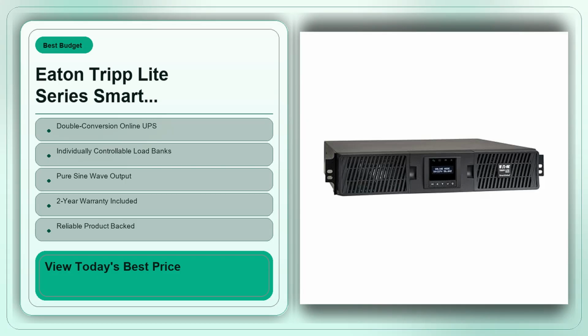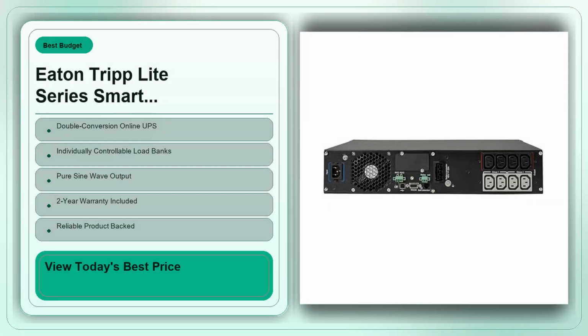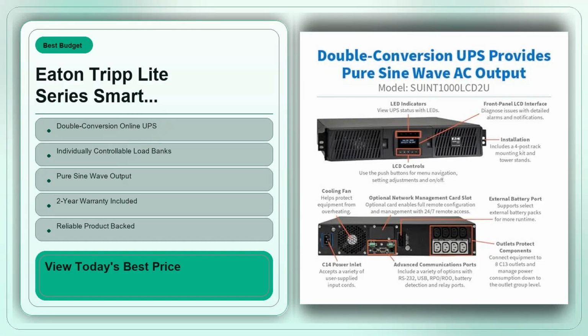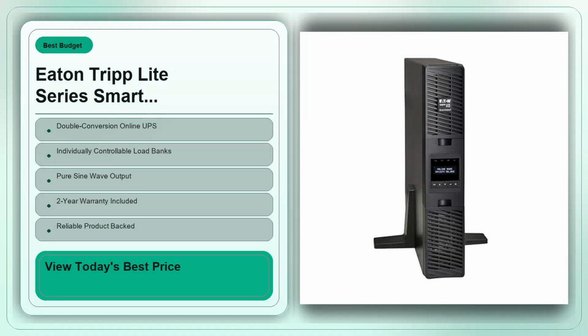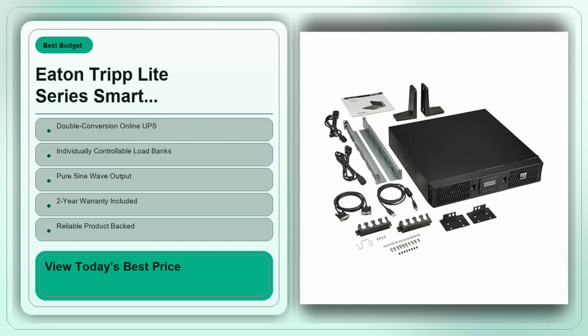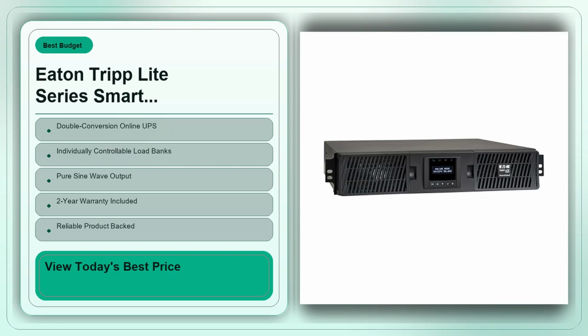One more nuance: the network card is optional, not standard. If you decide you need remote monitoring, you'll have to purchase the module separately. It's not a huge cost, but it's an extra step that can catch first-time buyers off guard. The installation is straightforward: just a PCIe slot in the back, but you do need to configure it within your network, which may involve opening ports or setting up SNMP credentials.